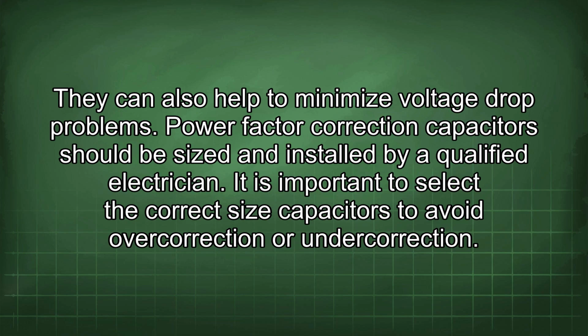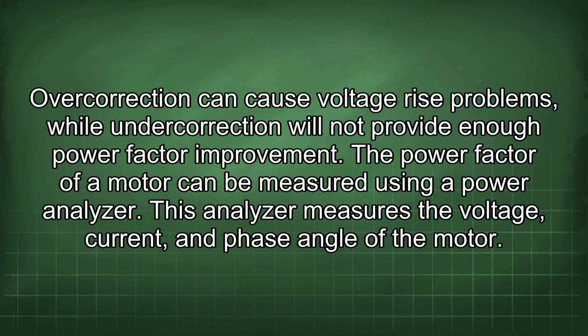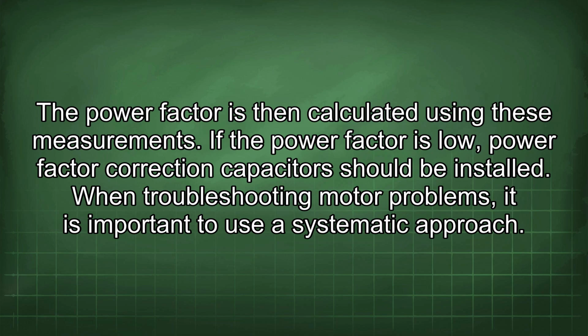They can also help to minimize voltage drop problems. Power factor correction capacitors should be sized and installed by a qualified electrician. It is important to select the correct size capacitors to avoid overcorrection or undercorrection. Overcorrection can cause voltage rise problems, while undercorrection will not provide enough power factor improvement. The power factor of a motor can be measured using a power analyzer. This analyzer measures the voltage, current, and phase angle of the motor. The power factor is then calculated using these measurements. If the power factor is low, power factor correction capacitors should be installed.